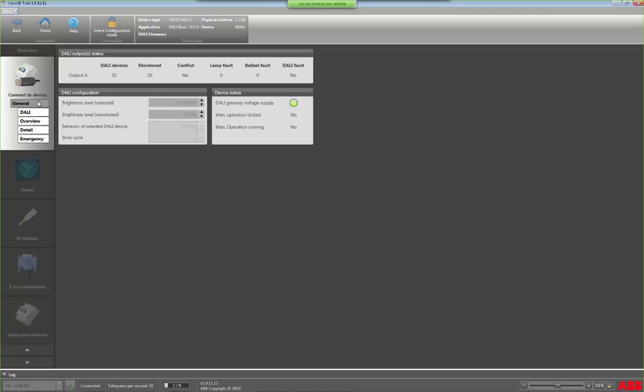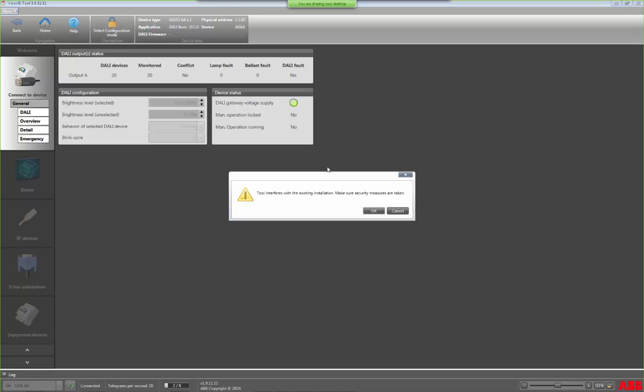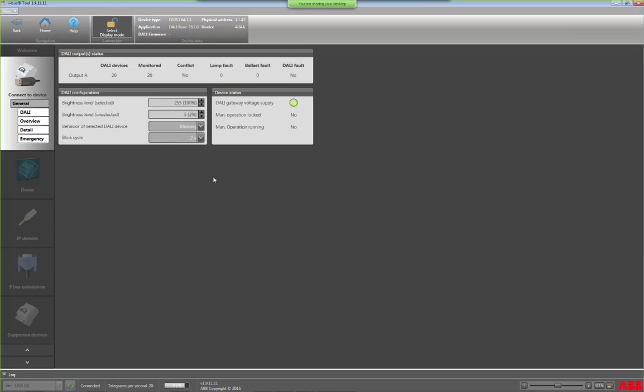A general overview of output A shows — for example — 20 DALI devices currently connected and monitored, with no conflicts, no lamp failures, no ballast failures, and DALI voltage OK. Clicking Select Configuration Mode gives access to the DALI gateway to send commands or link devices to a group. In this mode, when you select a device on the next page, you can switch it on and off, dim up and down, and blink the selected device. Be careful with blinking — only recommended for LEDs, not fluorescent lamps. You can set the selected device to 255 brightness and unselected devices to 5%.